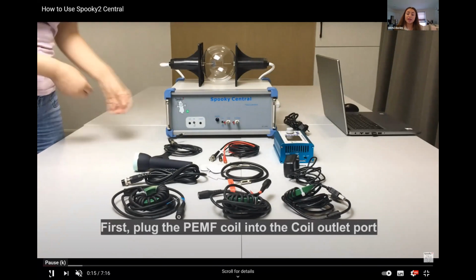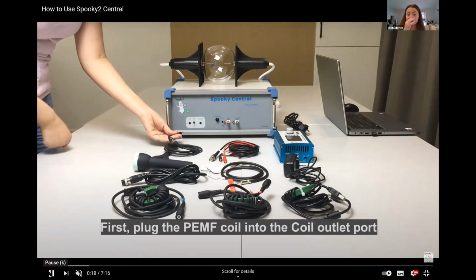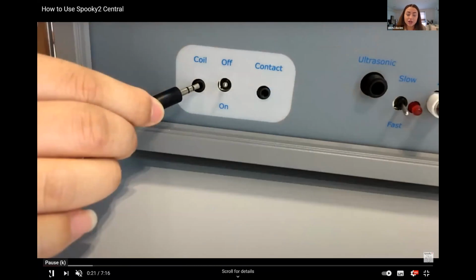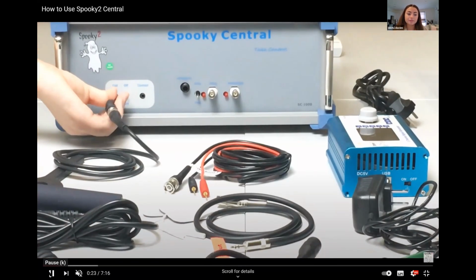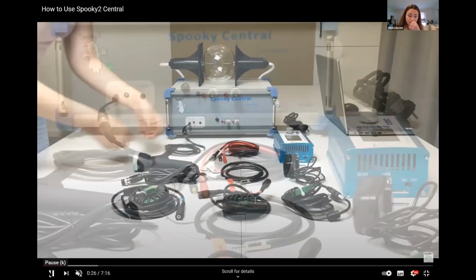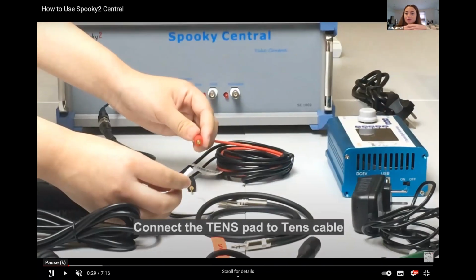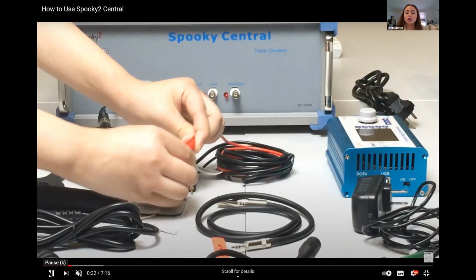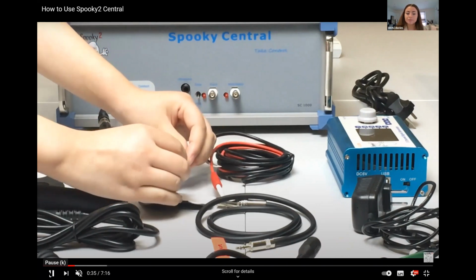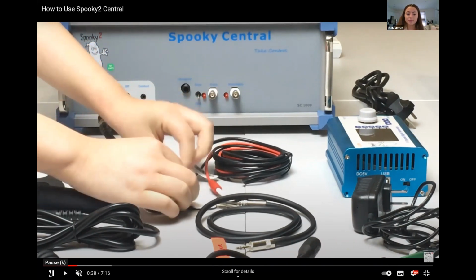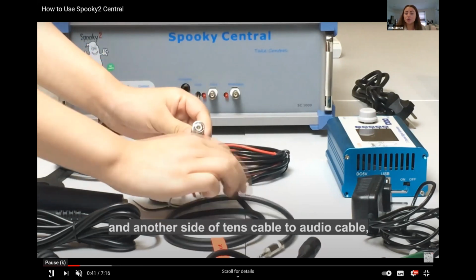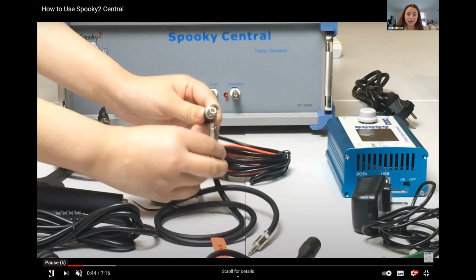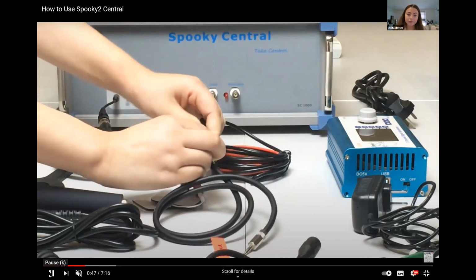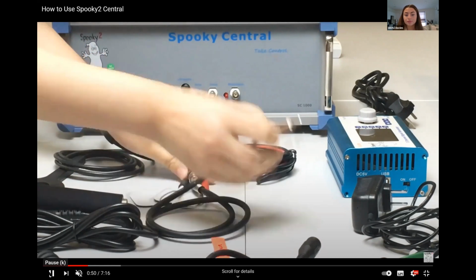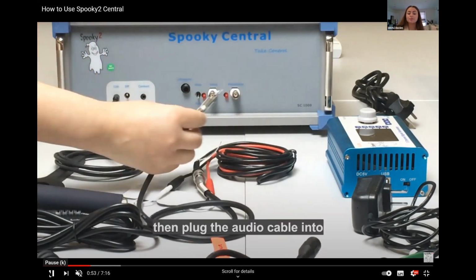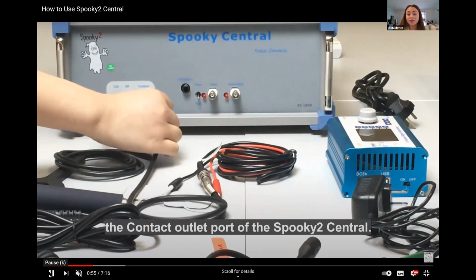So you would first take the PEMF coil into the coil outlet port as shown in the picture. You would then connect the TENS pads, or your hand cylinders or contact kit, to the cable, and the other side of the TENS cable to the audio cable that's provided with your Central kit. You would then plug the audio cable into the contact outlet port of the Central.